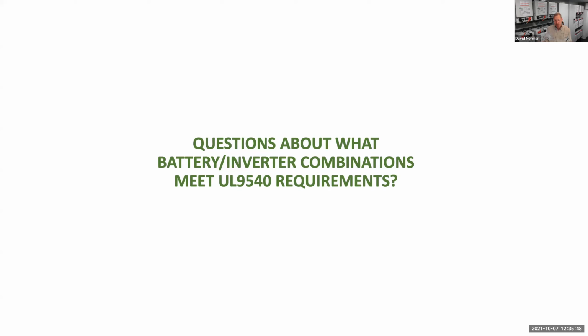9540, the standard as written by Underwriters Laboratory, is very specific. It says 20 kilowatt hours, and that's what we have tested to. Yeah. Like everything in life, the world is shades of gray. And this is a very much evolving standard as far as marrying UL 9540 with UL 9540A with UL 1973. There are a lot of moving pieces and parts, and there are even things being changed with UL 1973 because there are some things that are kind of contradictory in the code. So I think it's just going to take a year or so for this to really flush itself out.